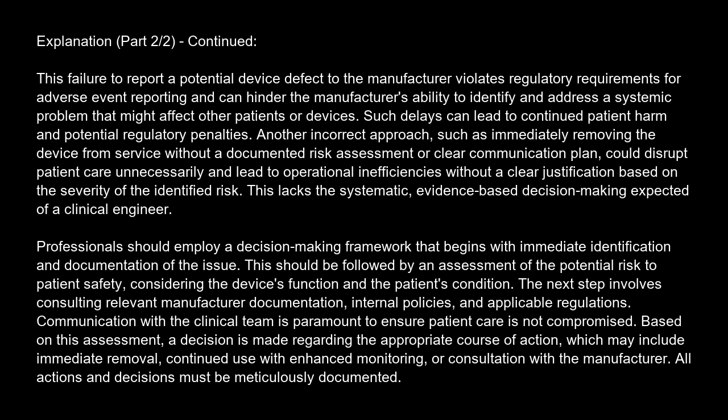Professionals should employ a decision-making framework that begins with immediate identification and documentation of the issue. This should be followed by an assessment of the potential risk to patient safety, considering the device's function and the patient's condition. The next step involves consulting relevant manufacturer documentation, internal policies, and applicable regulations. Communication with the clinical team is paramount to ensure patient care is not compromised. Based on this assessment, a decision is made regarding the appropriate course of action, which may include immediate removal, continued use with enhanced monitoring, or consultation with the manufacturer. All actions and decisions must be meticulously documented.